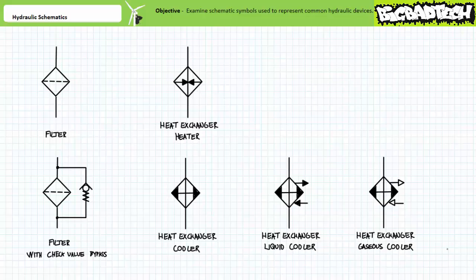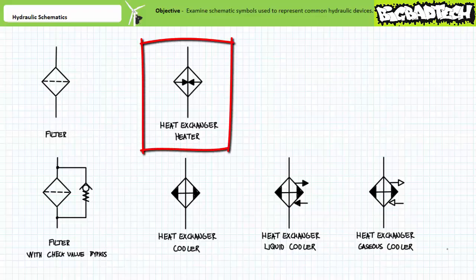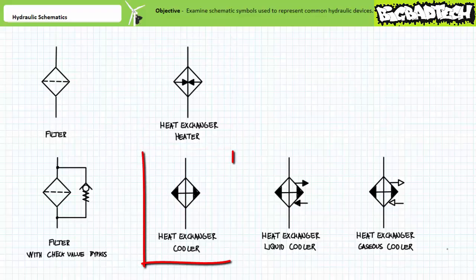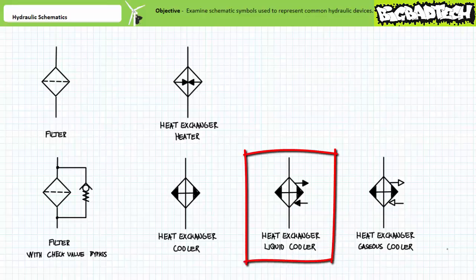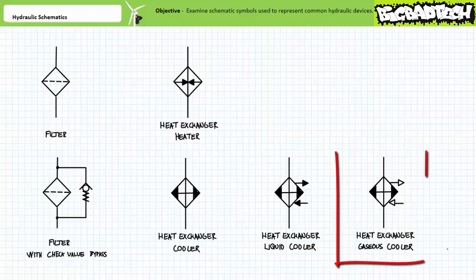Heat exchangers are also diamond-shaped. Heat exchangers come in two notable forms: heaters and coolers. A heater adds heat. The arrows point into the heat exchanger. A cooler removes heat. The arrows point away from the heat exchanger. Heat exchangers can use different mediums to conduct heat away from or to the fluid they're conditioning. This is a cooler that uses a liquid heat transfer fluid. Note the arrows are filled in. This is a cooler that uses gas as a heat transfer fluid. Note the arrows in a gaseous cooler are clear.